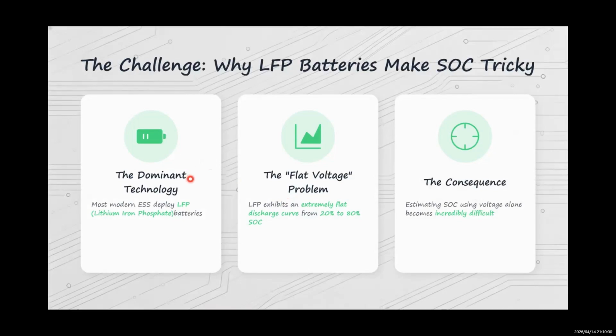Most of today's systems use LFP battery cells, lithium iron phosphate, which are great for safety. But they have a unique challenge because LFP has an extremely flat voltage plateau between 20% SOC and 80% SOC. So voltage barely changes in this range, so SOC estimation becomes really hard. Minor measurement errors will lead to significant inaccuracy in SOC estimation.